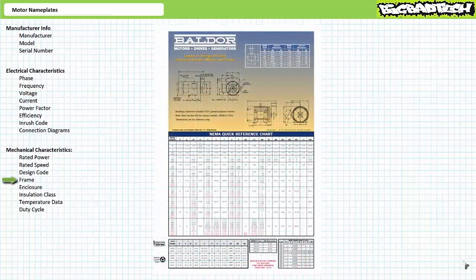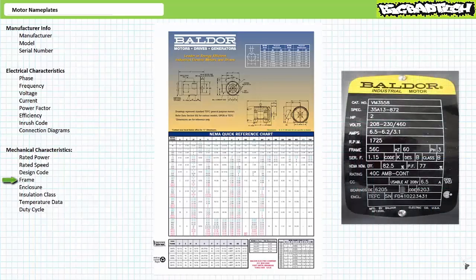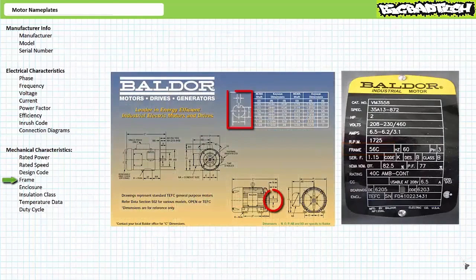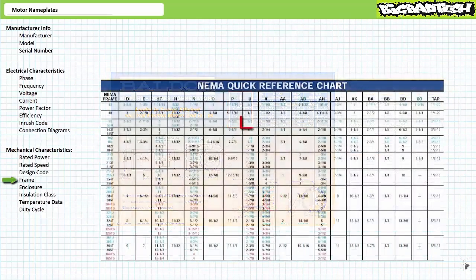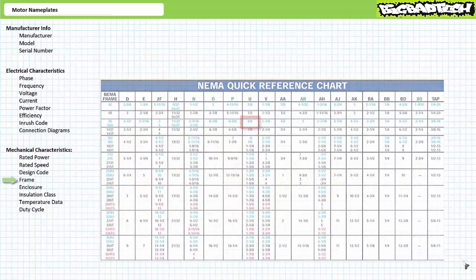The frame entry on a motor nameplate specifies dimensions of the motor as well as the locations and dimensions of the attachment points used to mount and properly secure the motor. There are NEMA and IEC frame charts available for cross-referencing these dimensions. For example, let's say we need to know the shaft diameter of this particular motor. The motor nameplate specifies a NEMA 56C frame. The diagram accompanying the NEMA motor chart identifies the shaft diameter as property U. It looks like a frame 56 motor has a shaft diameter of 5/8 of an inch.